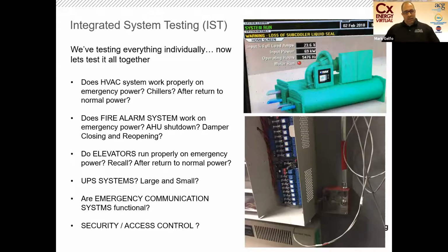But what I really want to talk about now, after Jesse's covered construction and the acceptance testing phase, is what we call integrated systems testing. Because now that we've tested all the individual pieces and parts of the emergency power system, and other people have probably tested the HVAC systems and other pieces and parts, it's time to test to make sure everything works together in all different modes. Just because things worked on utility power doesn't necessarily mean they're all going to work the same way when we're on emergency power, or after we've switched between branches of power, or switched back from emergency power to utility power, because things just don't always work the same way.